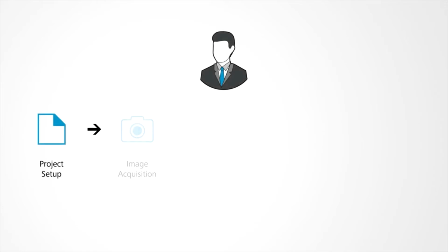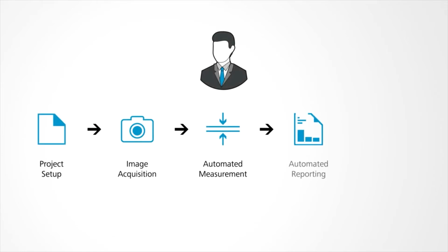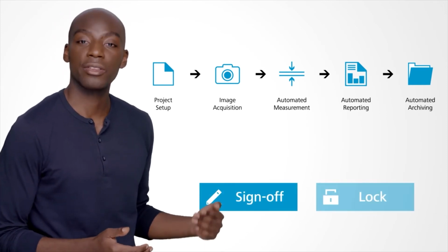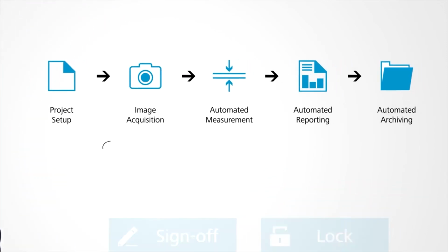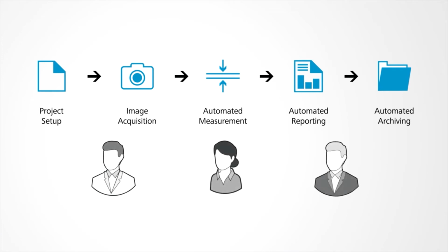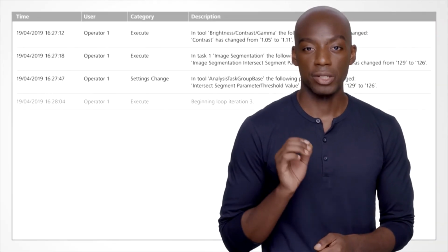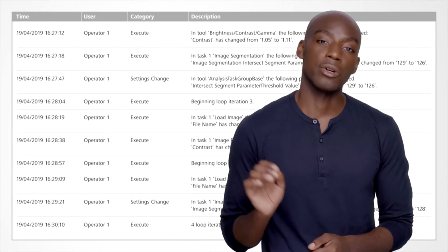A supervisor builds easy-to-follow guided workflows. All the Zeiss material modules, analytical tools, and microscope controls are available to use. Once created, the supervisor can sign off the workflows and lock them to prevent further edits. The operators run the approved guided workflows day to day. Every result is digitally signed by the user. Every change and input is seamlessly recorded, no extra effort is needed.